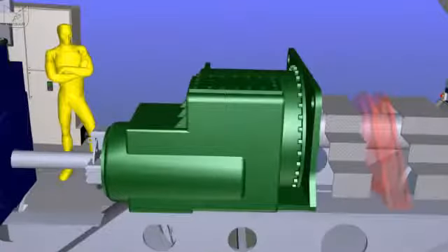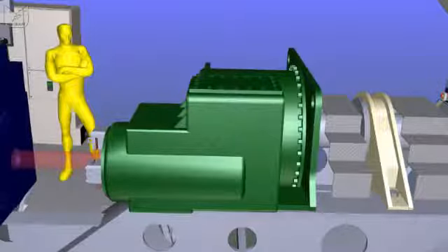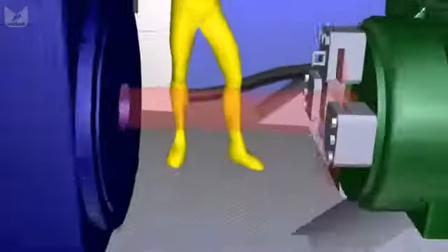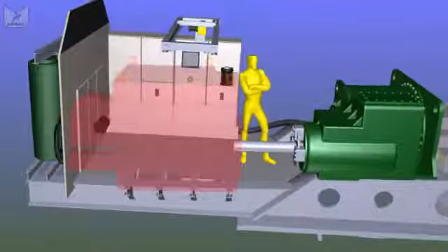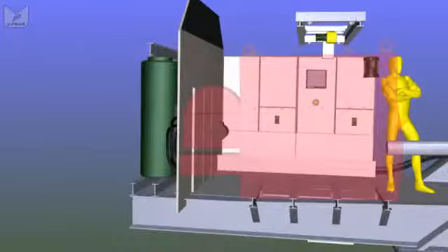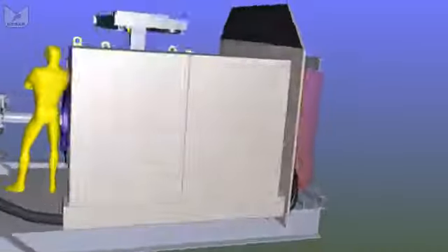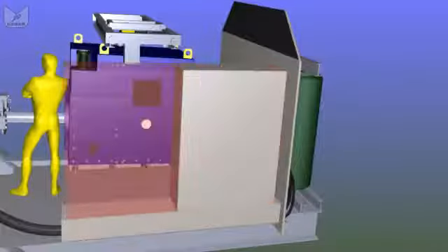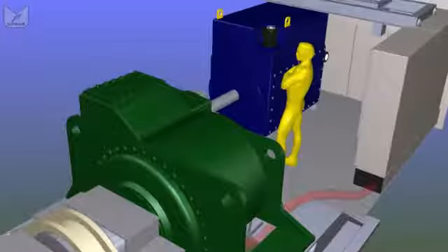So our main shaft drives our gearbox, which is mounted centrally because it's often the heaviest component. Out of the back comes a high-speed shaft, as before. That's where the braking system is. High-speed shaft then drives the generator, which is usually oil-filled. The generator then supplies 690 volts, in this case into our transformer, which is sitting right next to it. That high-voltage signal then passes through the switchgear and the cabinets, down the dropper cable, straight down to the bottom of the tower, through those switches on platform 2 and off to the substation. And that, as an overview, is pretty much all there is to it.